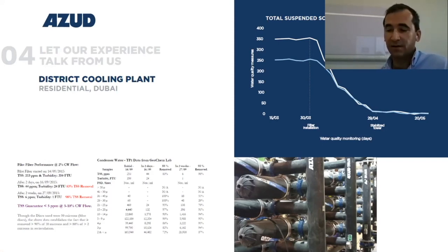We decreased the maintenance, which used to be 4 to 5 hours per week because of the problems caused by the sandstorm. We increased the lifespan of nebulizers and panels, and all of this with a return on investment in less than 2 years. So as you can see, only installing one filtration equipment in this big cooling tower meant a relief for the factory and important savings in terms of money for the DCP.